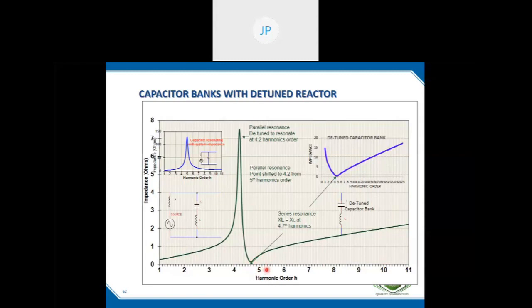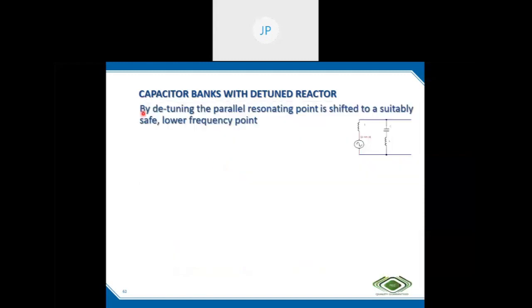But detuned capacitor banks are normally intended for use in a harmonic environment within the limit. Harmonics are not exceeded, they are within limit. But to protect the capacitor bank from the resonating point, we can see the explanation here. By detuning, the parallel resonance point is shifted to a suitably safe lower frequency point.